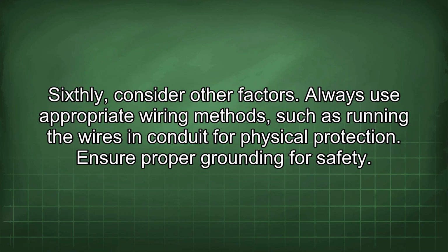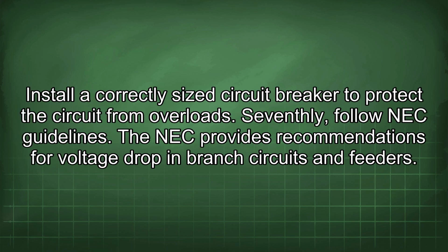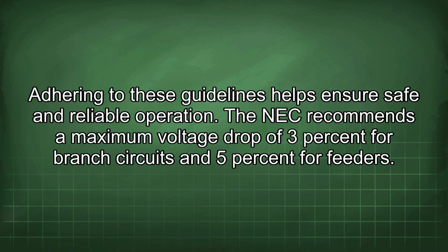Sixthly, consider other factors. Always use appropriate wiring methods, such as running the wires in conduit for physical protection. Ensure proper grounding for safety. Install a correctly sized circuit breaker to protect the circuit from overloads. Seventhly, follow NEC guidelines. The NEC provides recommendations for voltage drop in branch circuits and feeders. Adhering to these guidelines helps ensure safe and reliable operation.